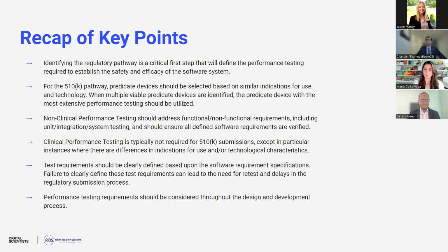Otherwise, you might have to repeat these after you have the final device nailed down, in case the test environment, the test requirements, the acceptance criteria, or the qualifications of the test group are not defined. You'll either need to justify those or run that test through a more formal quality management system defined test process.